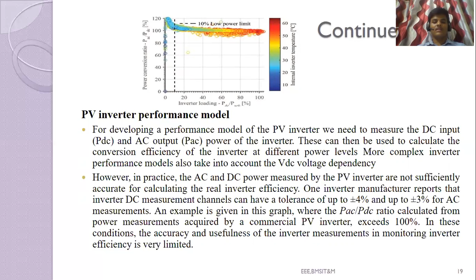As in the graph, the PAC and PDC ratio calculated from the measurements obtained by the PV inverter exceeds 100%. In these conditions, the accuracy and the usefulness of the inverter measurement in monitoring efficiency is very limited. As we move on, such measurements can still be used to develop simple energy performance models that, to some extent, estimate inverter efficiency degradation due to faults relative to the initial performance of the inverter.